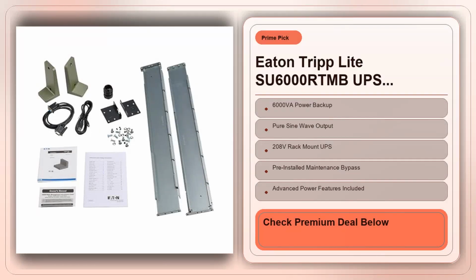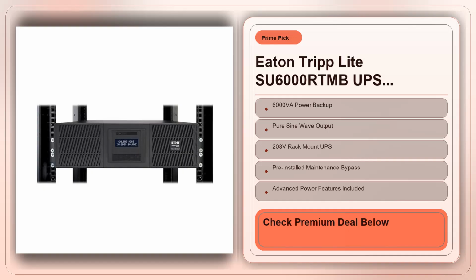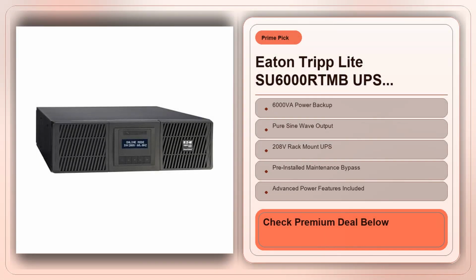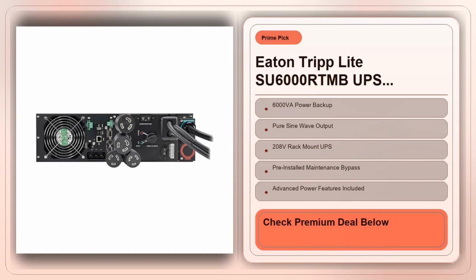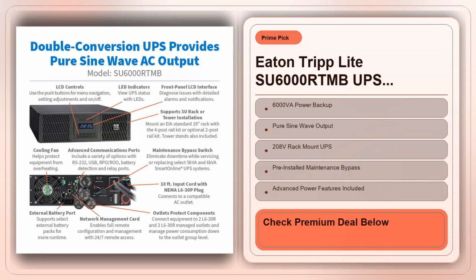6000VA sounds massive, but the usable wattage cap is 5400W, and that's the realistic limit you can draw before the UPS starts to droop. In a typical SMB setup, a couple of 1U servers at 300W each, a switch cluster at 100W, and maybe a backup NAS at 250W will sit well under that ceiling, leaving you enough headroom for temporary load spikes when you spin up additional VMs.